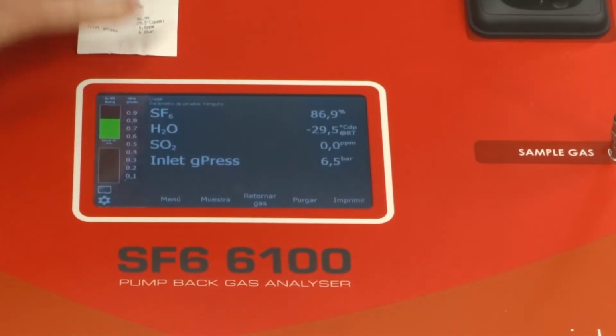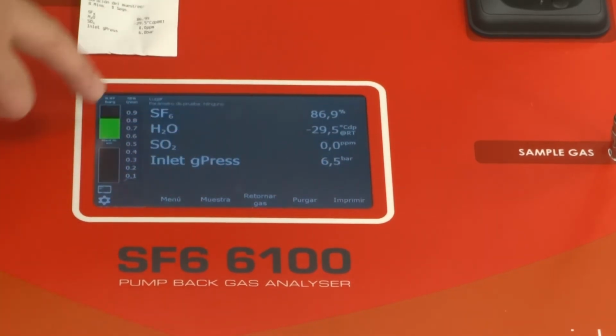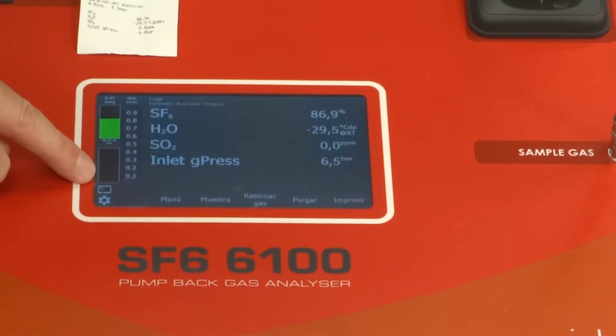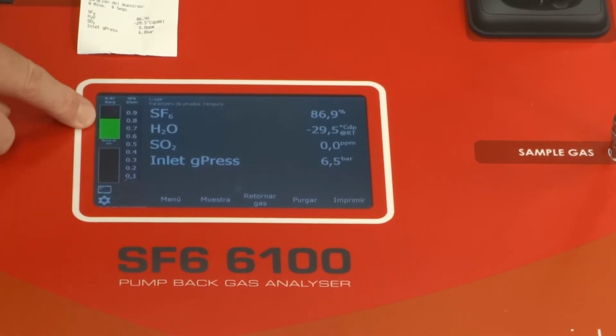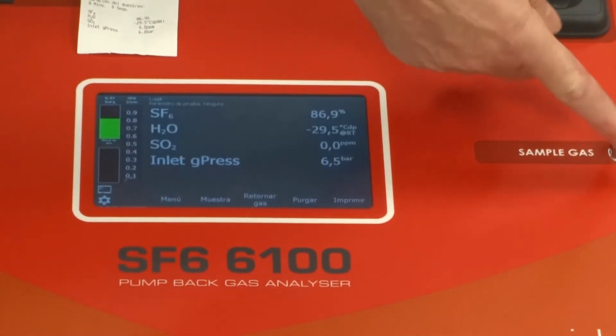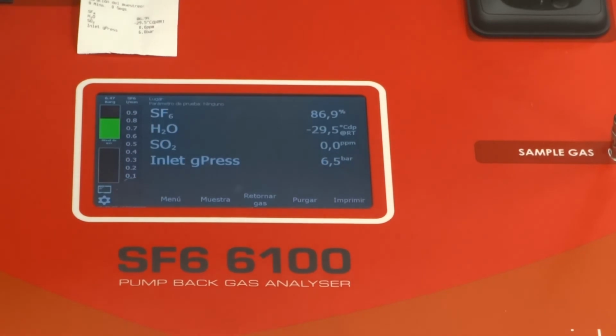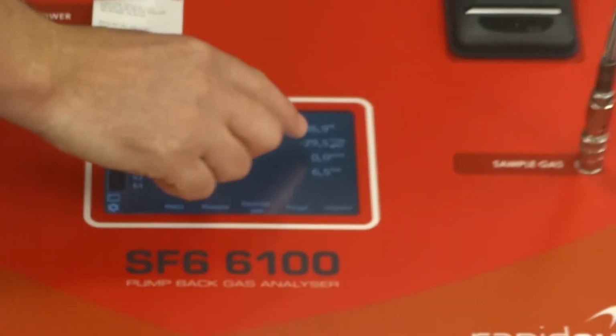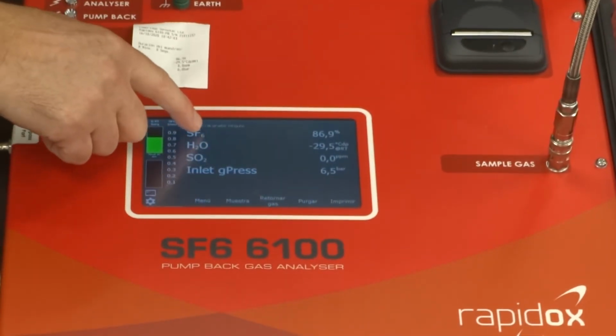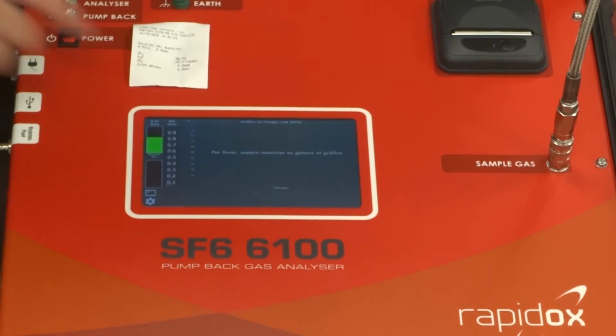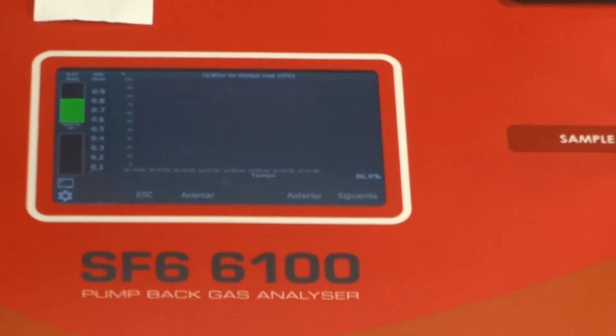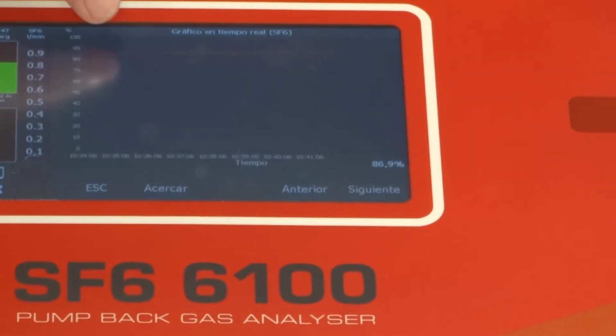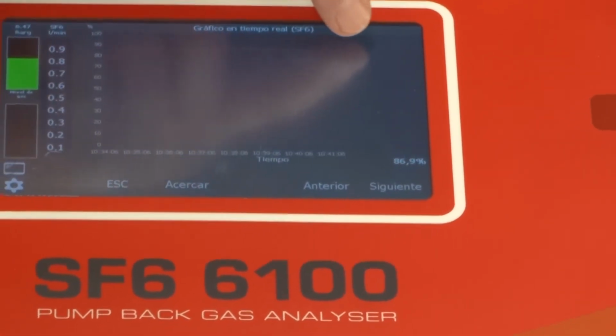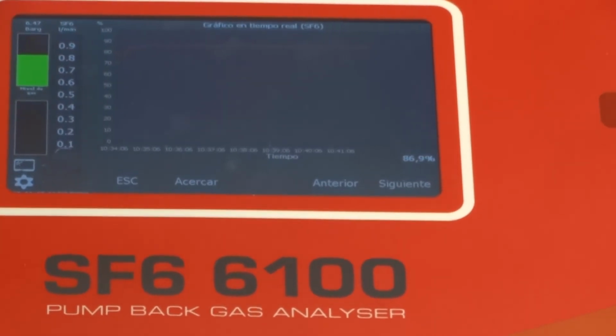Now, on this panel here, you can see that the gas bag is now empty. There is still a bit of pressure inside the hose, of course, because this is still pressurised, which is why it's very important that on the next test you perform another line purge. The readings are tappable, so if I press anywhere here where it says SF6, it will show me the SF6 results. And you can see that the reading was nice and flat on the infrared sensor after about 60 seconds.